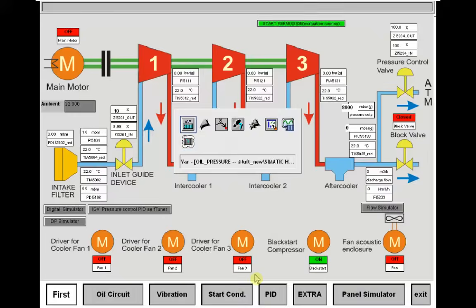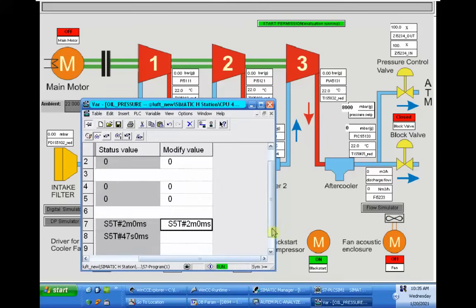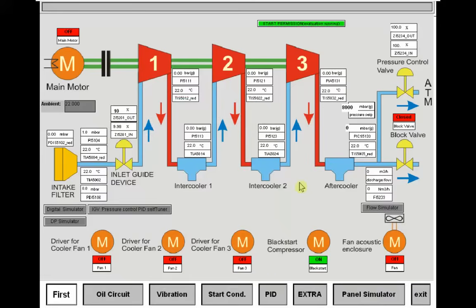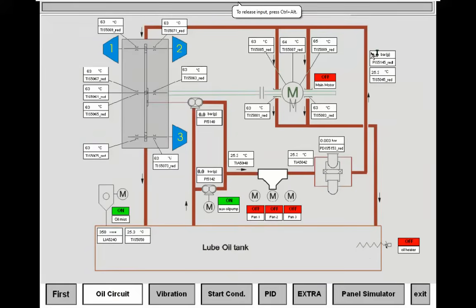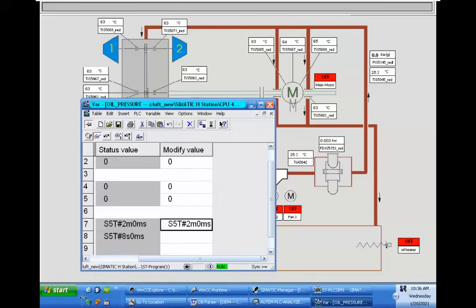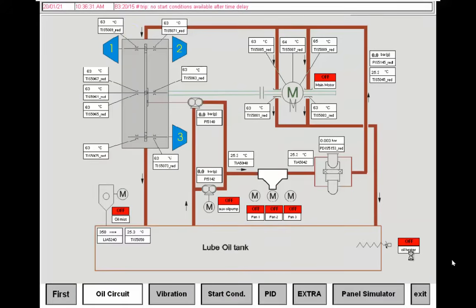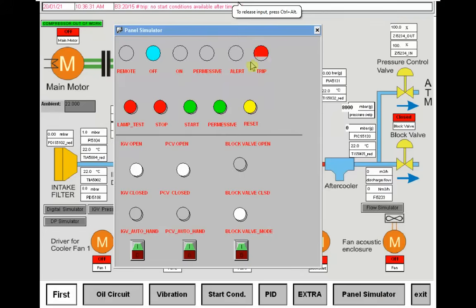Let me monitor the time here — this is the timer related to permission. When we lose this and the permission timer is expired and all of these conditions are not met, it's not possible to start the compressor. The oil pressure is totally linked to these redundant transmitters here, and you can see that after the timer expires the permissive will be shut down — trip, no start condition available after time delay. You can see that the trip is blinking and the compressor is in off mode.